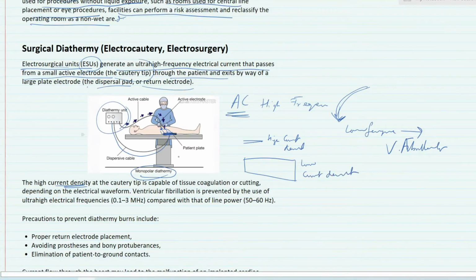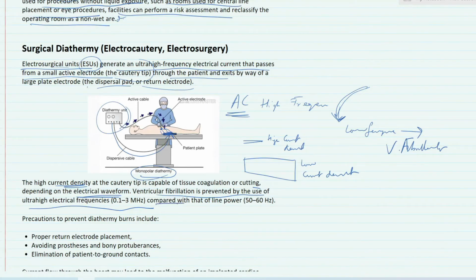And so if by some fault the plate comes off and we have a small area sticking to the patient instead of this large area, this can also lead to a burn here, right? So the high current density, as we have discussed, means the cautery tip is capable of tissue coagulation or cutting depending on the electrical waveform. Ventricular fibrillation is prevented by the use of ultra high frequency, 0.1 to 3 megahertz, compared to that of the power line, which is 50-60 hertz, as we've already discussed here.